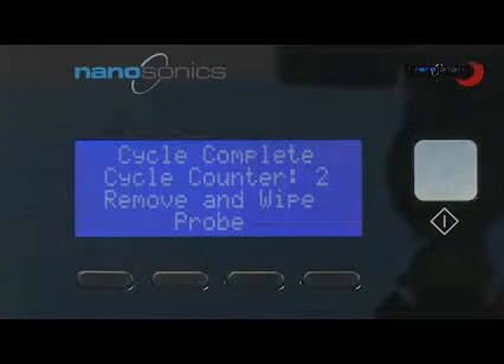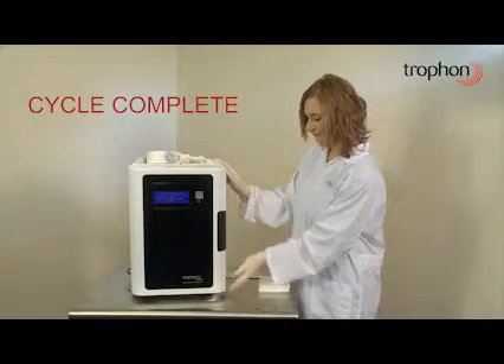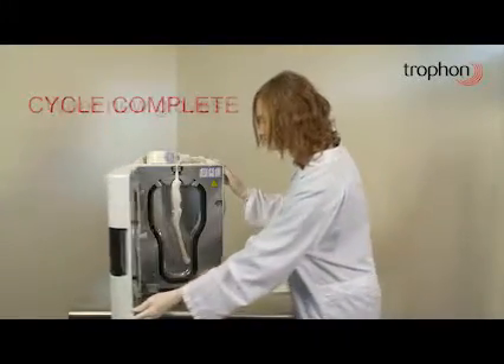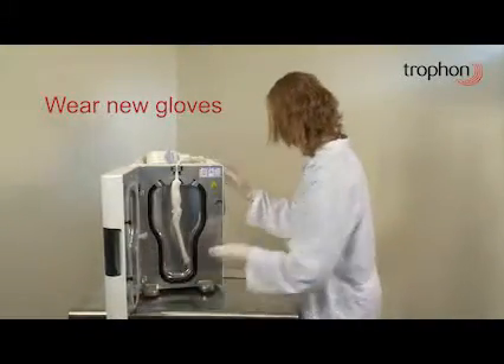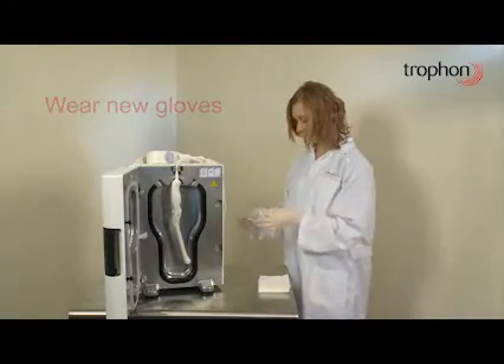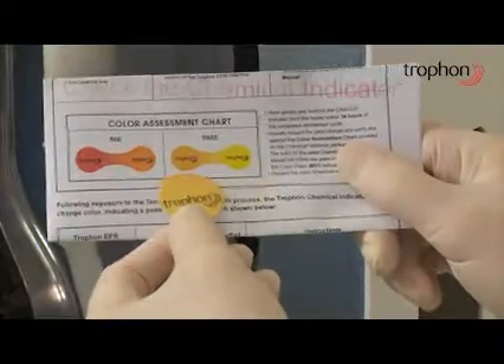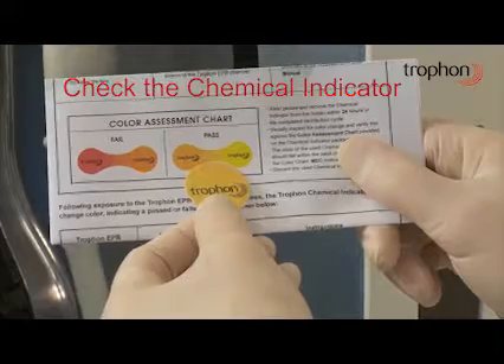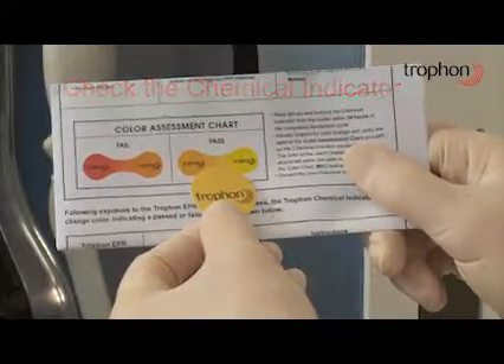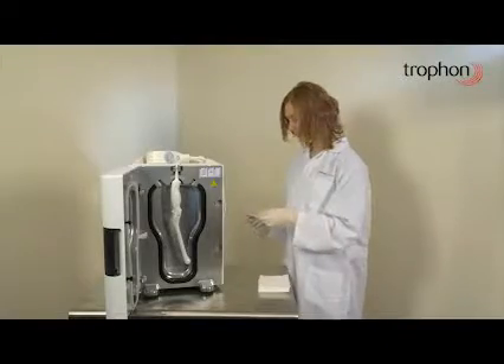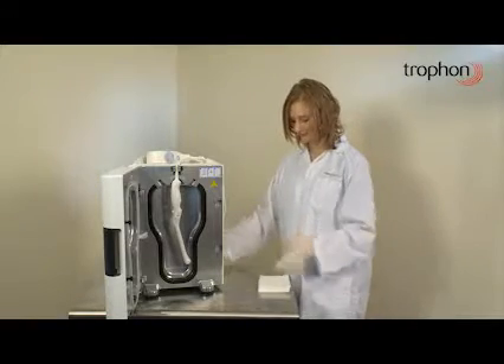Upon completion, open the chamber door. Wear new gloves to protect the probe from contamination. Remove the chemical indicator and compare it against the color chart. If a pass color is shown, no further processing is required. Discard the used chemical indicator.